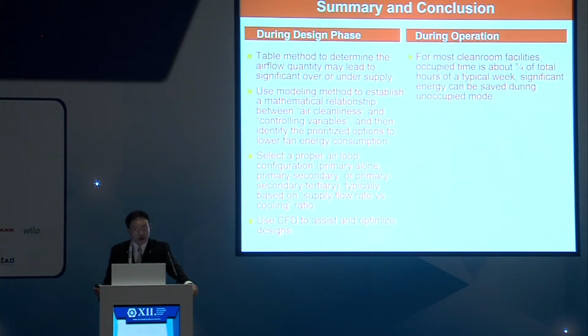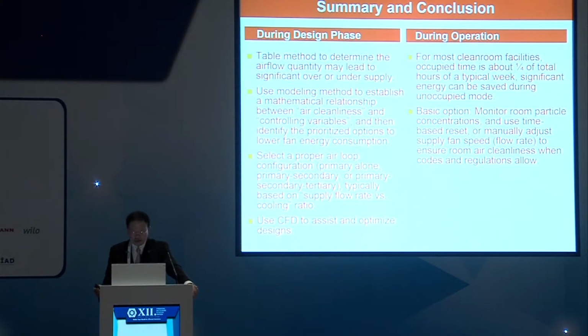During operation, there is a lot of chance to reduce the energy consumption. For most clean room facilities, occupied time is about 25%. The rest is considered unoccupied. Significant energy can be saved during unoccupied time. A basic option is to monitor room particle concentration and use time-based reset. Time-based reset is basically based on the time clock. During occupied time, you provide a high airflow rate. During unoccupied time, you reset to a lower rate. The level to set is based on prior data or operation. So you can identify that during occupied I need this amount of air change rate, and during unoccupied I can reduce down to level B.